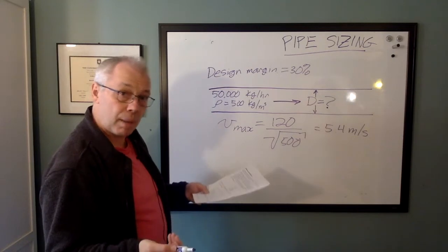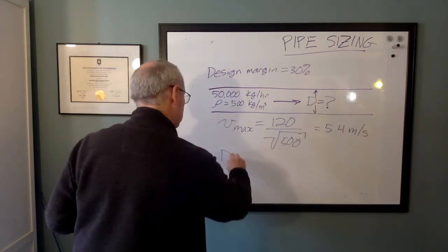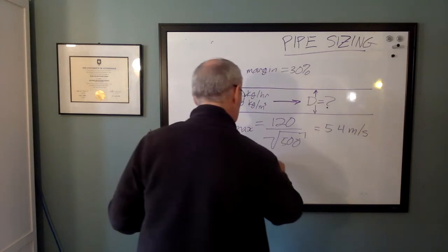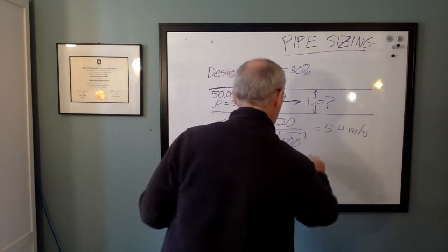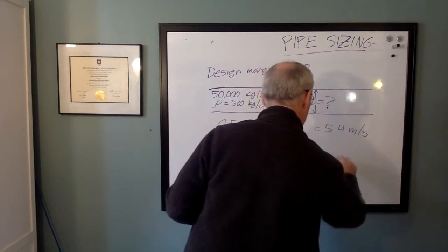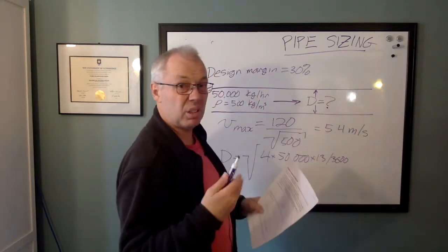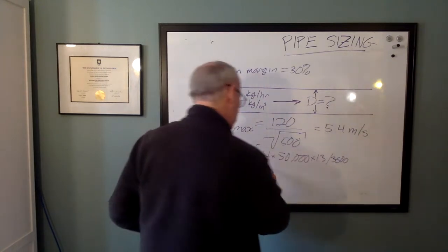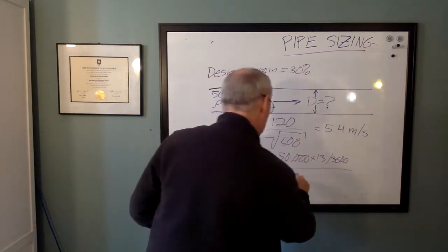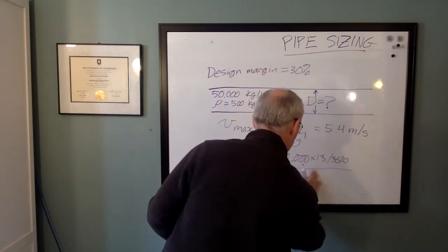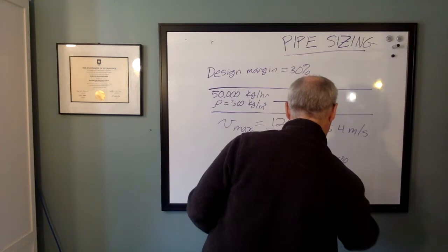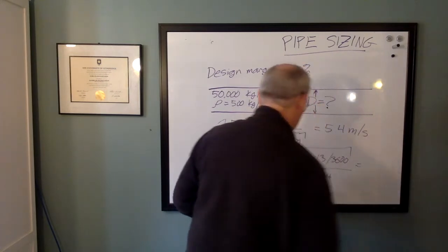So now we can calculate the diameter. The diameter is equal to the square root of 4 times 50,000 times 1.3, divide that by 3,600 to convert everything into kilograms per second. And we're going to divide that by 500 kilograms per meter cubed. We'll throw a pi in there. And our maximum velocity. And the diameter is 0.0926 meters or about 92.6 millimeters.